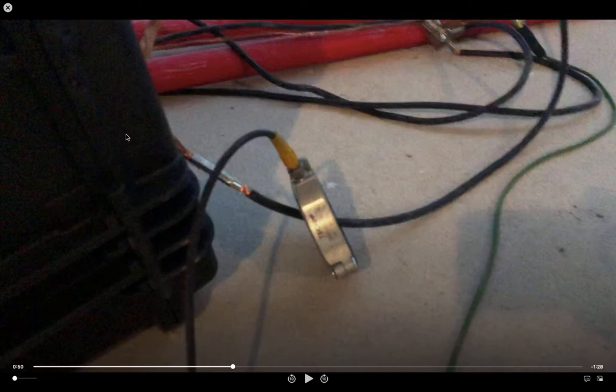Why do we have two sensors? Well, first of all, I'm going to say that this sensor is called HFCT - high frequency current transformer. You will see that this is also a coaxial cable which has a yellow marking, and later you will see how they are connected to the acquisition unit. This second sensor is put around the grounding wire of the cable we are testing.